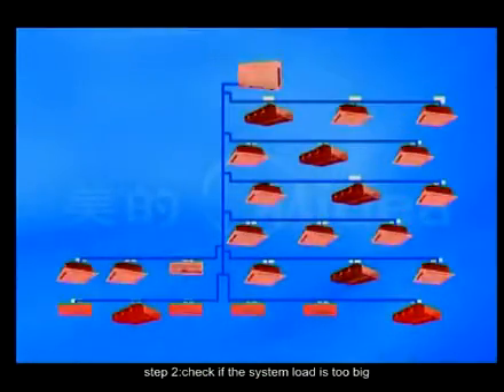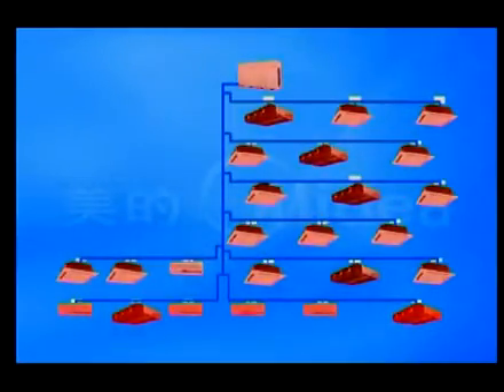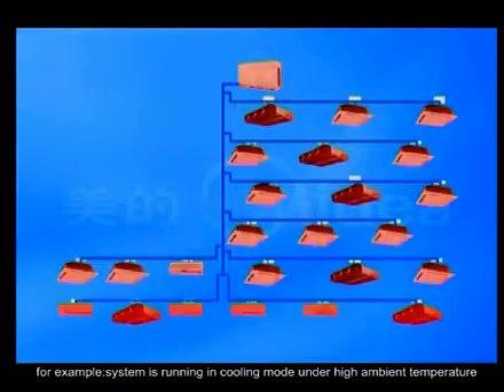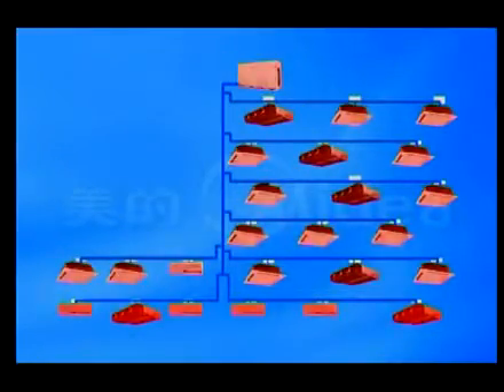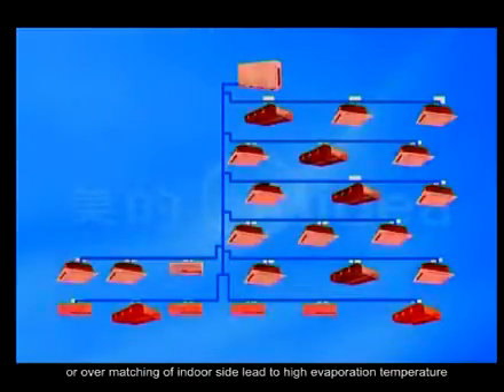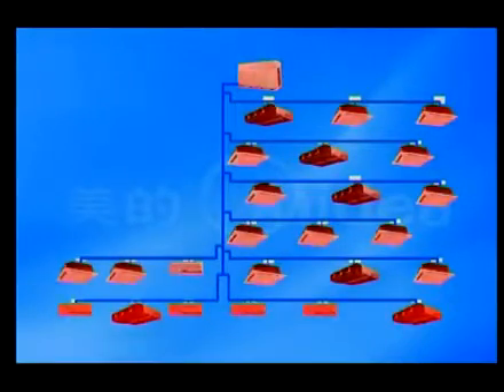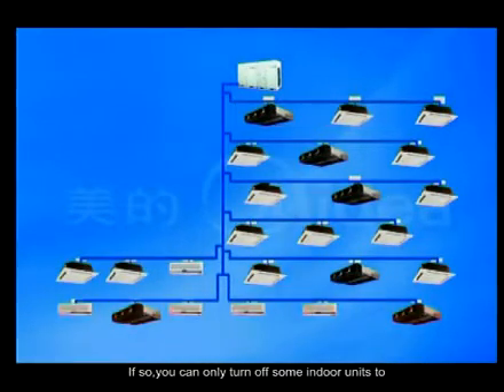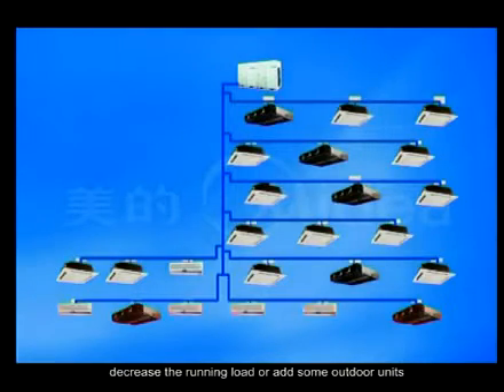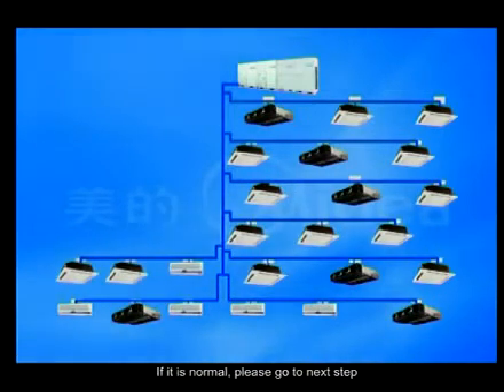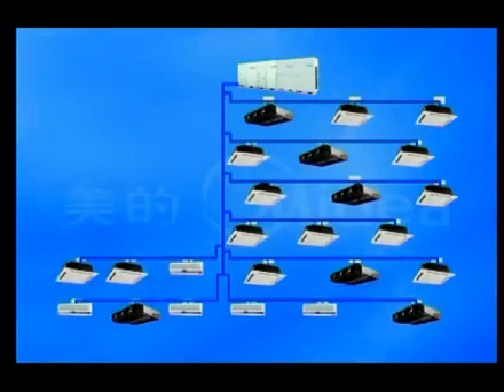Step 2. Check if the system load is too big. For example, the system is running in cooling mode under high ambient temperature, or overmatching of the indoor side leads to high evaporation temperature. If so, you can turn off some indoor units to decrease the running load or add some outdoor units. If it is normal, please go to the next step.